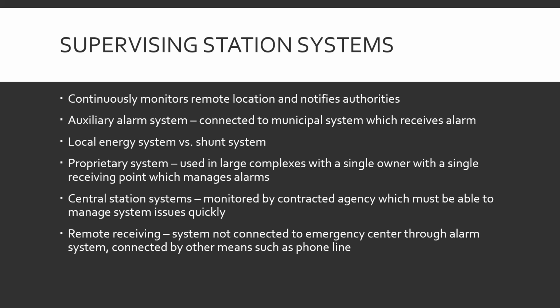Auxiliary alarm system. Connected to the municipal system, which receives the alarm. What that means is the fire alarm panel in the building, whatever building you want to imagine, a hospital, doesn't matter, is tied into the dispatch emergency communications system. A little thing goes off at dispatch, and they go, there's a fire alarm at this building. All right, page out the fire department. That's directly tied into the 911 system, if you will.